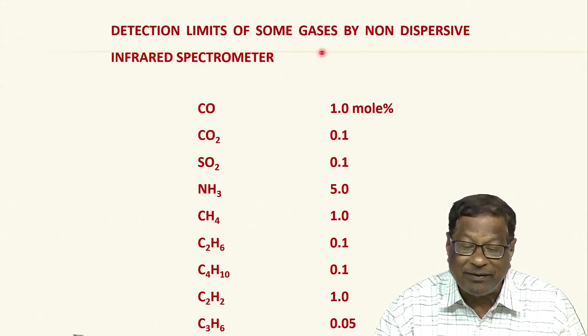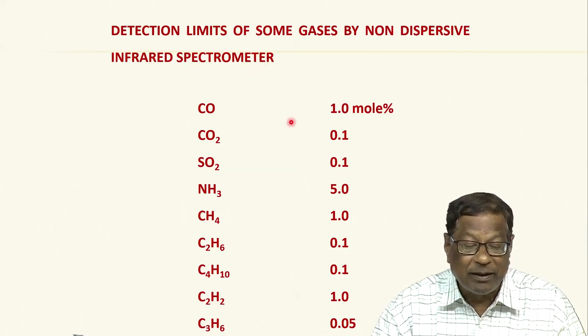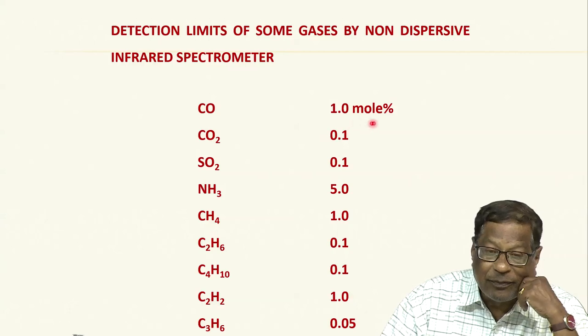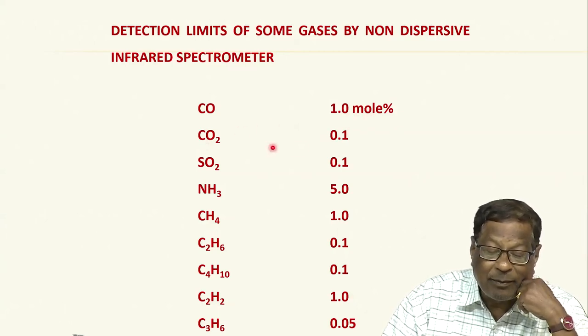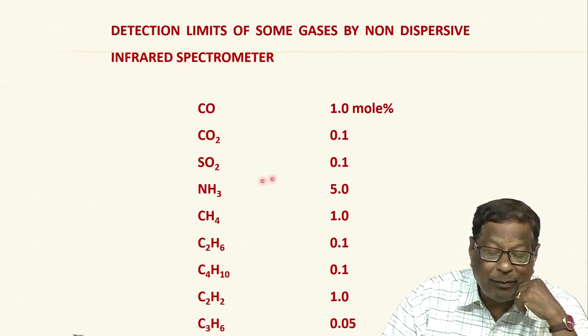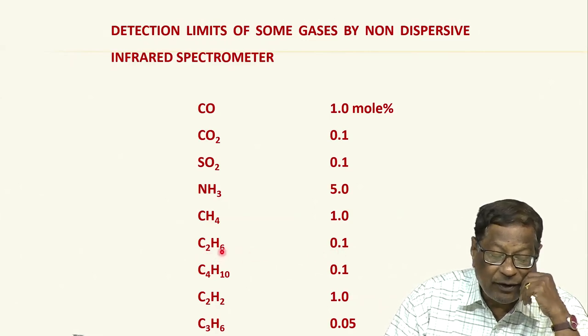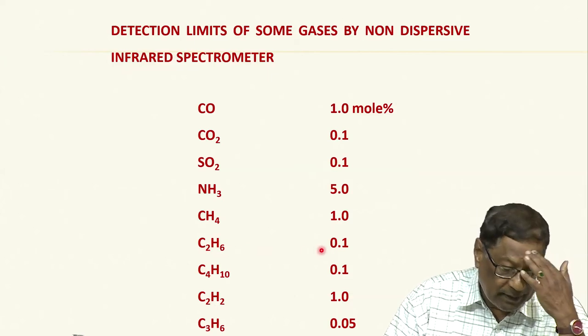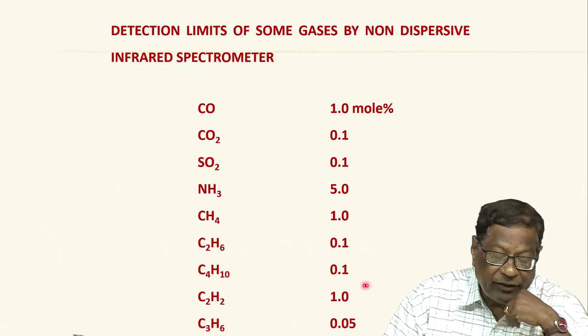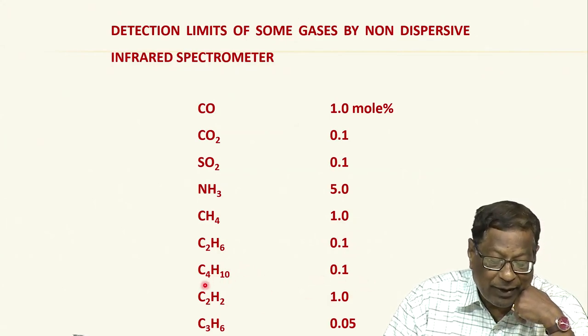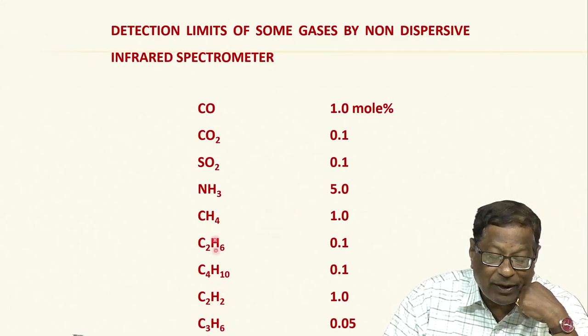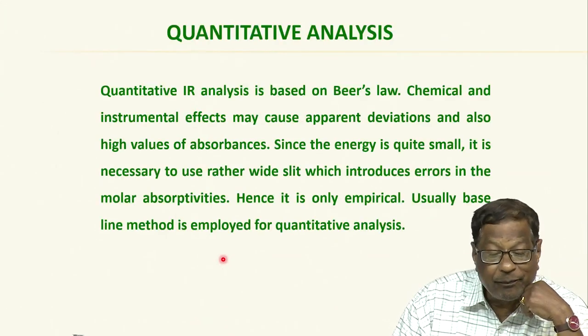Detection limits of some gases of non-dispersive infrared spectrometer: CO can be determined at 1 mole percent, CO2 at 0.1 mole percent, SO2 at 0.1 mole, ammonia at 5 mole percent, CH4 at 1 mole percent, C2H4 ethylene at 0.1 mole, C2H6 ethane at 0.1 mole, C4H10 at 0.1 mole, and C2H2 at 1 mole percent. These are methane, ethane, butane.